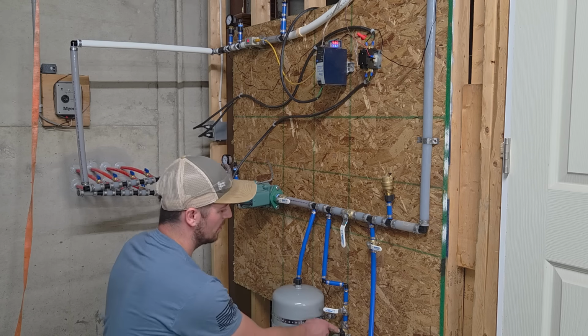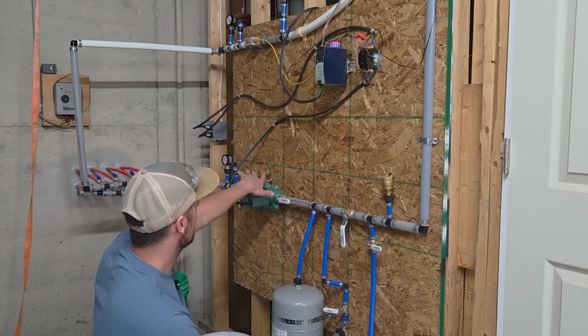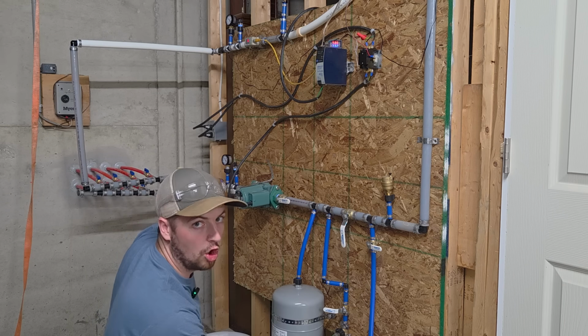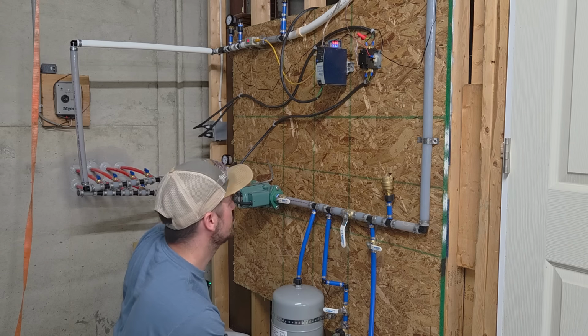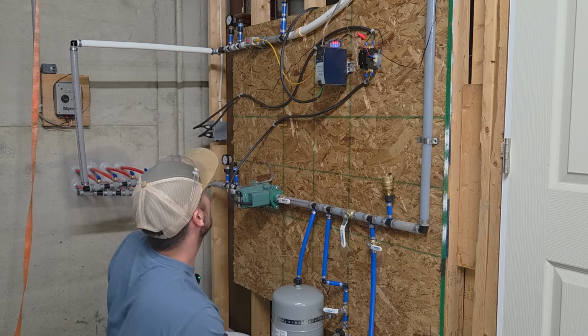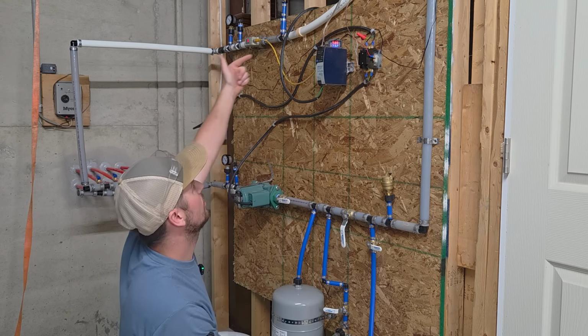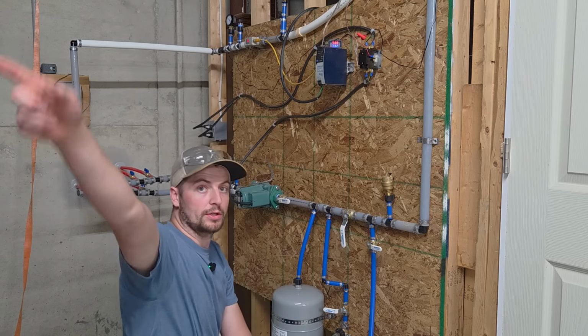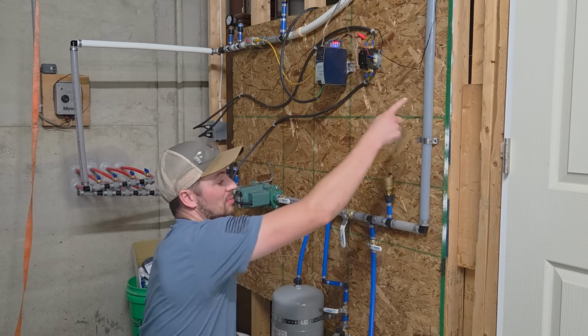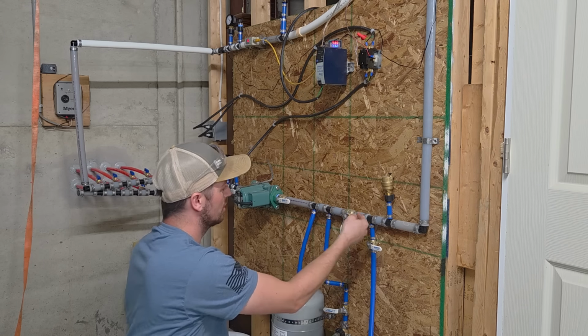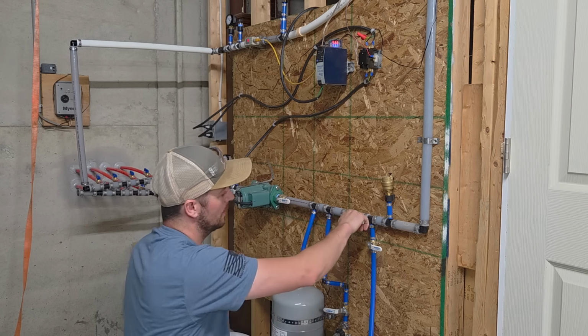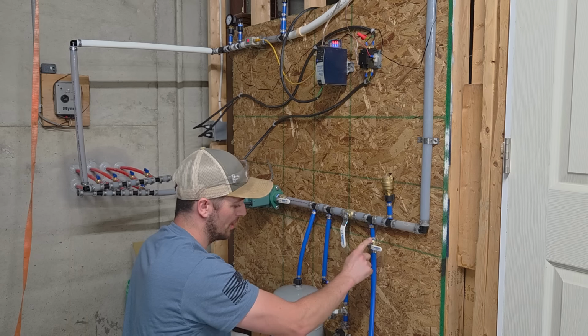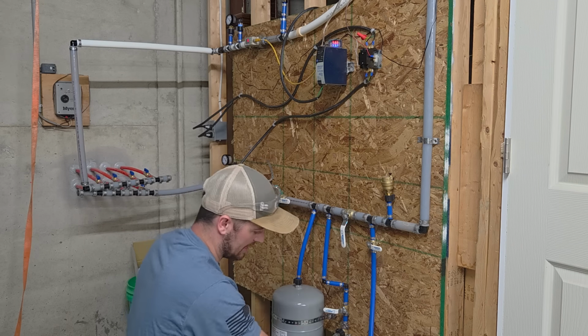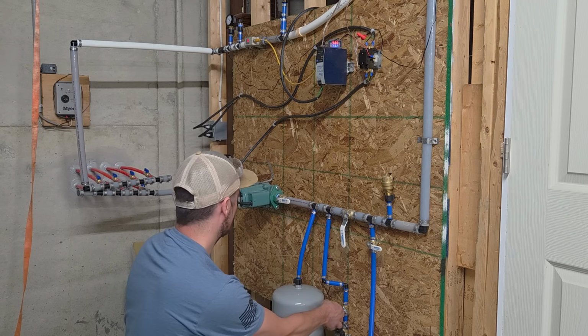So water goes in this hose here. It turns left here, goes by the pump, goes through all 4 of the ground loops at the same time. They're all parallel. And then it comes back through the top here, over to the heat exchanger and the plenum. Then it comes back down this line and it usually recirculates if this ball valve is open. But because I have this closed, and I'll open up this one, which will send it down and out to my sprinkler. Let's see what happens.